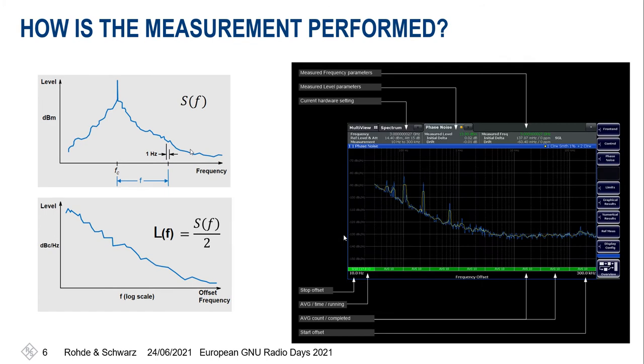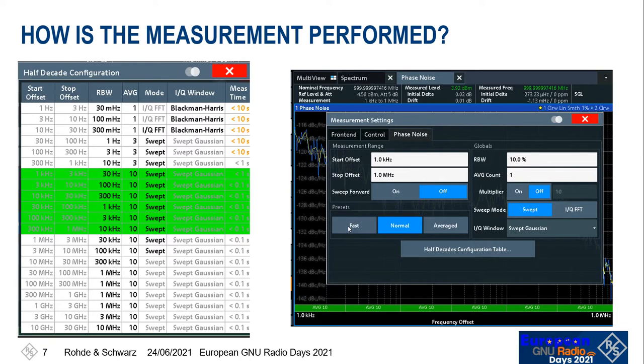When we look at this on a spectrum analyzer, we see these half decades. We see the phase noise plot against these half decades, and it's very typical to see the phase noise rising as it approaches where the carrier would be. Inside the analyzer, for this classical method called swept mode, we have these half decades growing smaller as we go closer to the carrier. Supporting the measurement in these half decades are bandpass filters — or resolution bandwidth filters — which are also decreasing in size as we get closer to the carrier.